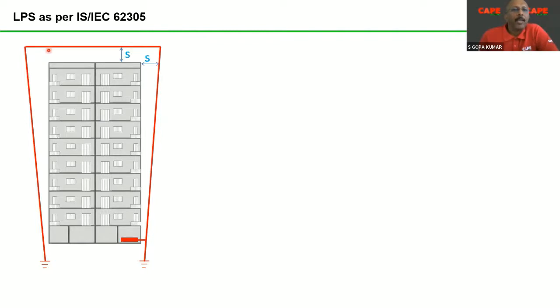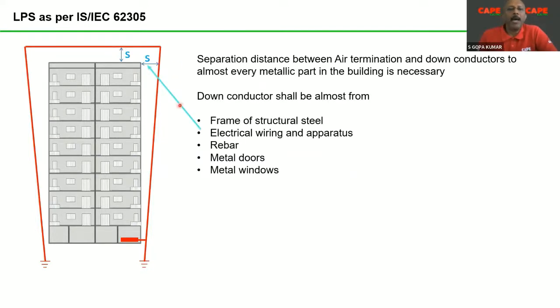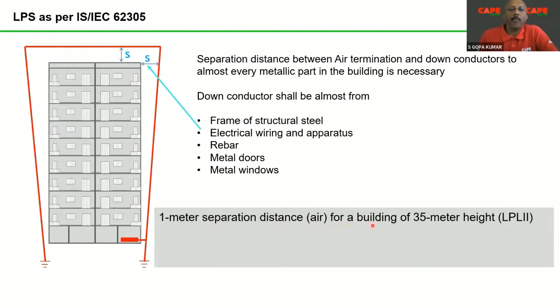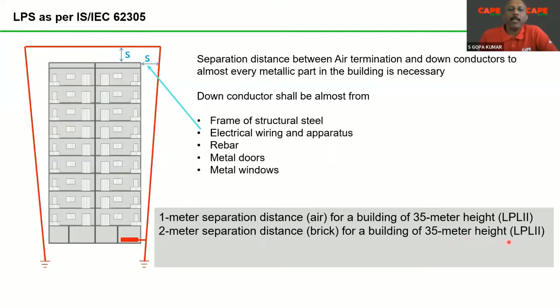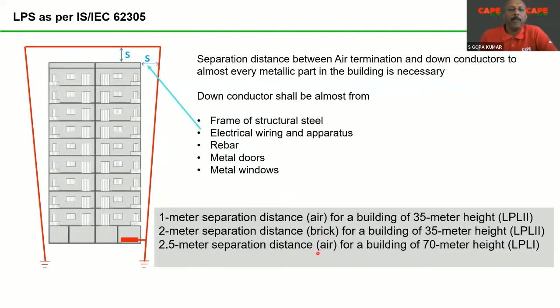What does this mean? The air termination mesh and the rod and parts of the down conductor: at the bottom you have equipotential bonding. Away from the equipotential bonding, the distance increases, and at the roof of the building a certain distance in meters is required between the air termination, or the parts of the lightning protection system, and the building material. How far is it? 1 meter separation distance for a building with a 35 meter height, level 2, the previous case which I explained. 2 meters if the insulation material is actually brick, not air. 2.5 meters in air if your building is 70 meters height, and 5 meters if your building is 70 meters height and the insulating material is brick.